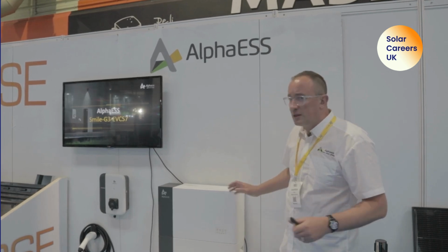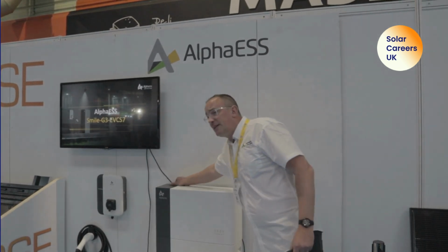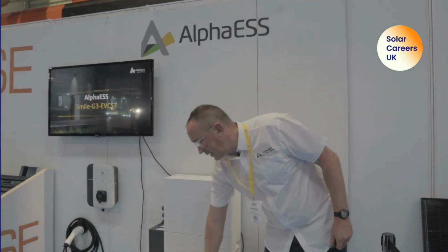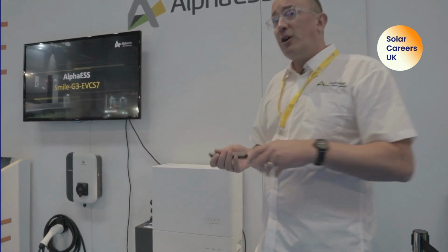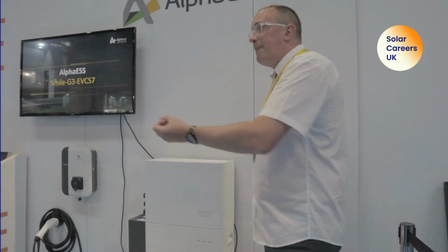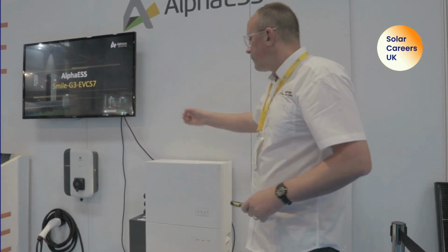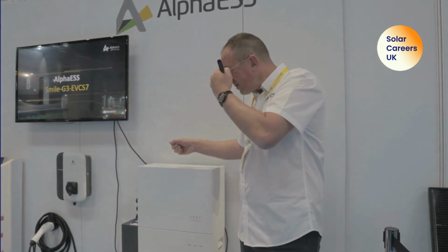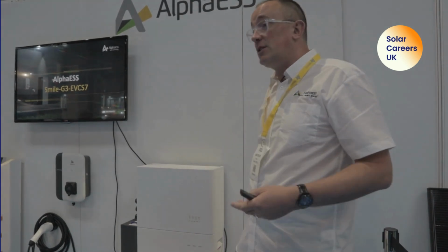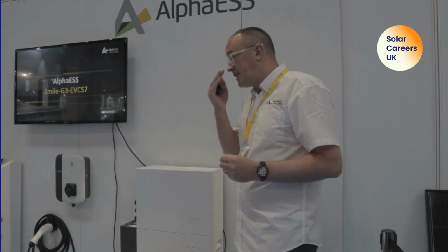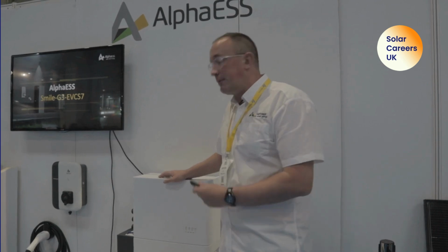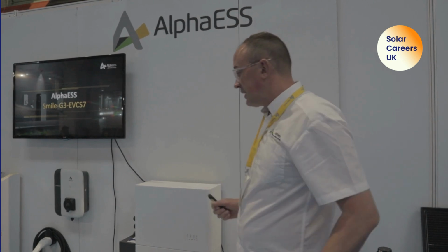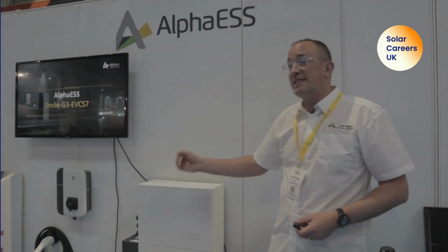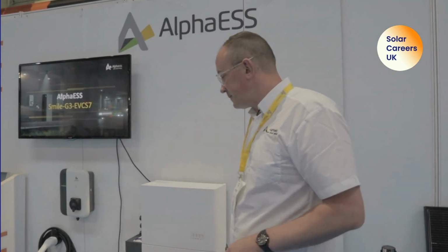Once we've installed the unit on the wall, we need to connect up our AC supply. There's a plug for the AC supply, so you can wire that up away from the unit and plug it in, so you're not fiddling about underneath. There's another plug for the backup port. The hybrid inverter has 2 MPPTs on there. We need to make sure our voltage range for those MPPTs is between 100 and 550 volts. We can take up to 15 amps on the MPPT. And we've got our battery connection, so we need to connect to that first battery with our positive cables, and we need our BMS cable, a data cable for the BMS to go into the EMS board.